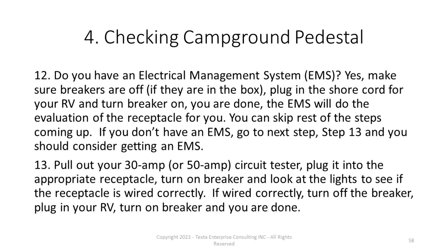Step 13, pull out your 30 amp or 50 amp circuit tester, plug it into the appropriate receptacle, turn on the breaker, and look at the lights to see if the receptacle is wired correctly. If wired correctly, turn off the breaker, plug in your RV, turn on the breaker, and you're done.